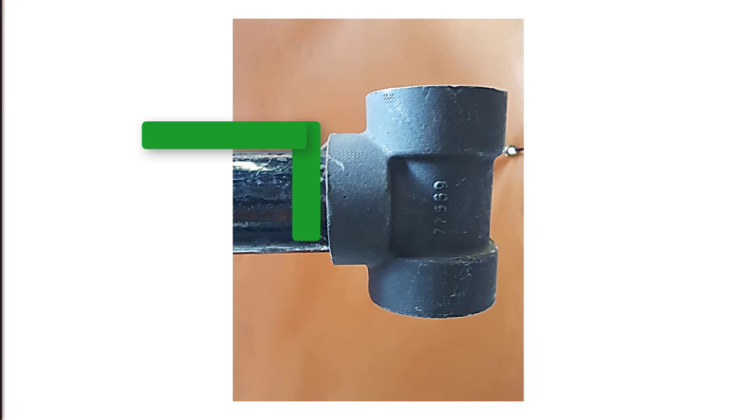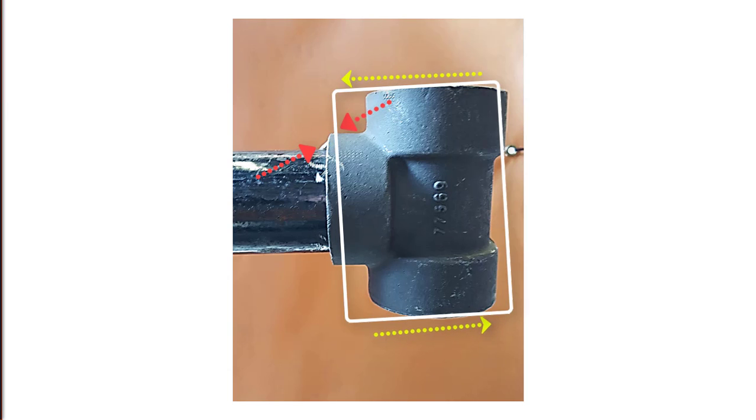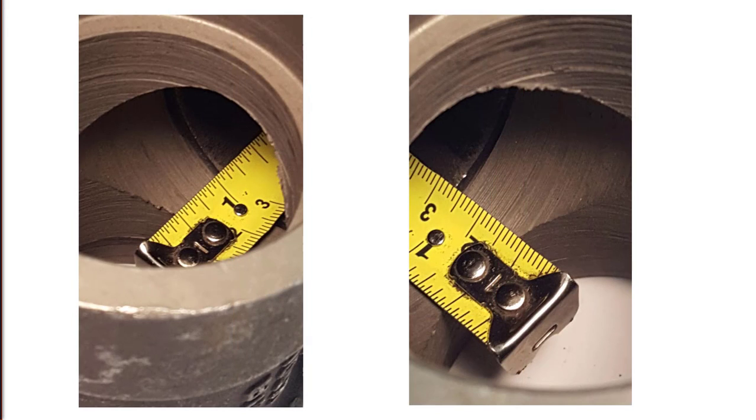I want to talk about the weld pulling process that you feel. If we had not opened up that side where we placed our first tack, the weld would have pulled us out of square and the fitting would be bound out of square. Notice that this procedure has opened the inside bottom, shown on the left. So we now have a small even expansion gap of about 1/16 of an inch or 1.5 millimeters all the way around the inside of the fitting.